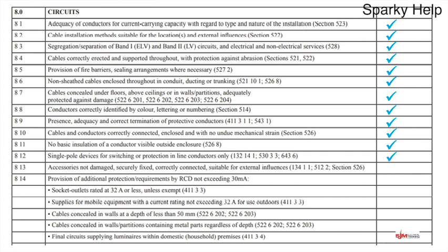Accessories — not damaged, securely fixed, correctly connected, and suitable for external influences. All the accessories and everything you've fitted — does it meet those requirements? Is it securely fixed, or if you slam the door will it fall off the wall? If it's going to do that, go back and put some more grip fill on it. External influences again are about being suitable for the location in which it is installed.